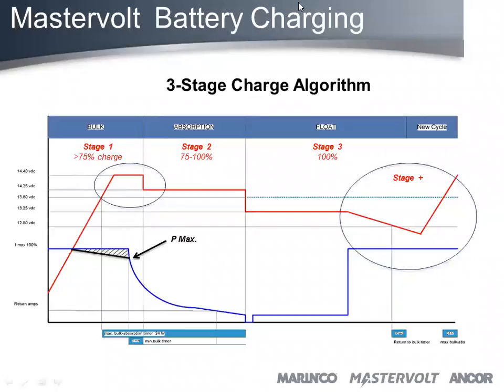At this point, the battery starts filling up to 100%, and the current starts to drop when you get down to about 6% of its maximum output. So if you have a 100 amp charger, that's about 6 amps. At that point, it says the battery is full, in my opinion, and I'm going to float.